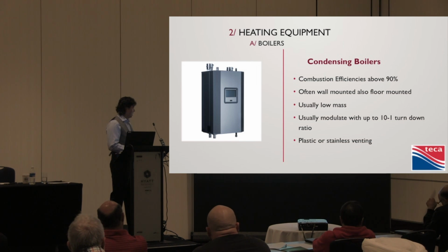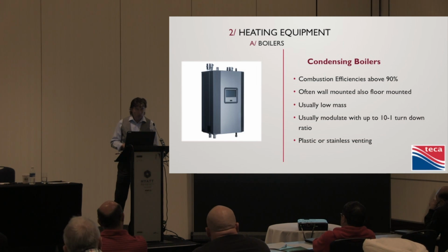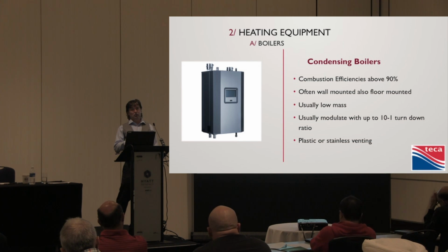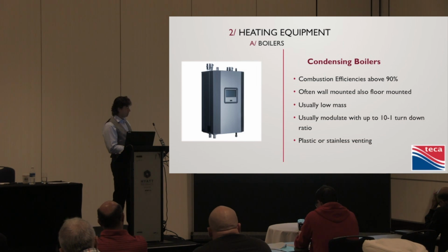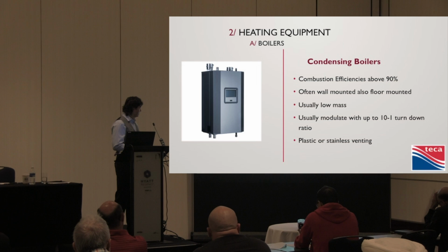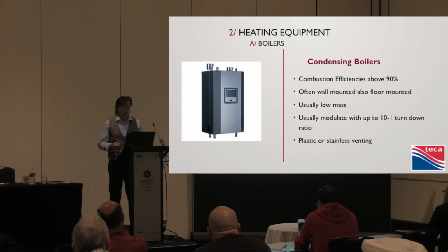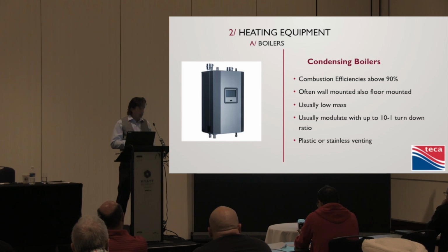Modulation, up to 10-to-1 turn-down ratio. That's fairly common. So if it's a 399,000 BTU boiler, it should go down to 39,900 BTUs. Yeah? 10-to-1 turn-down ratio, 1/10 of the capacity. So it'll modulate in steps. And that's kind of critical. We'll talk about that actually shortly too.